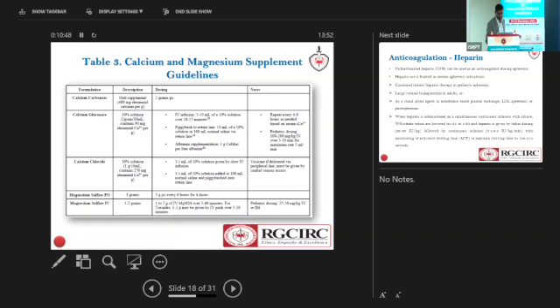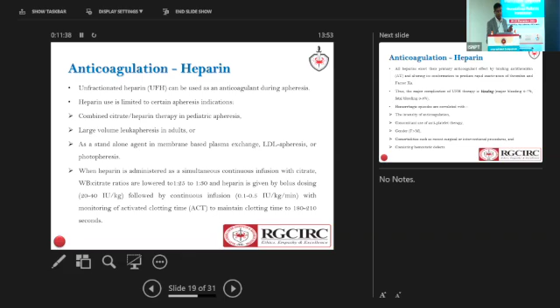Coming to heparin-type anticoagulation, mostly unfractionated heparin is in use, but it is limited to certain indications. You can combine it with citrate in large volume leukapheresis, and if using it alone, we can use it in membrane-based plasma exchange where the flow is high, and in LDL apheresis and photopheresis. When we are using heparin along with citrate, the whole blood to AC ratio we tend to set as low as 1:25 to 1:30. And then after that, heparin bolus followed by continuous infusion of heparin. And we have to monitor the activated clotting time at 180 to 210 seconds.